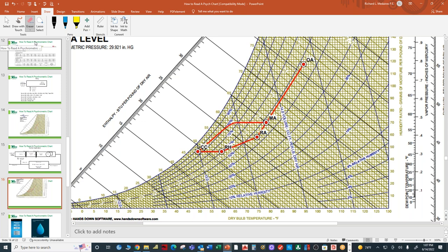And that condenser water temperature is 95 degrees Fahrenheit. And you can see in this little example where we're reheating the air from roughly 50 degrees Fahrenheit up to 60. And so our approach temperature is 95 minus 60, which is 35 degrees. So there's plenty of capacity in the condenser water to reheat the air for free. So in our case, that's what we would do.